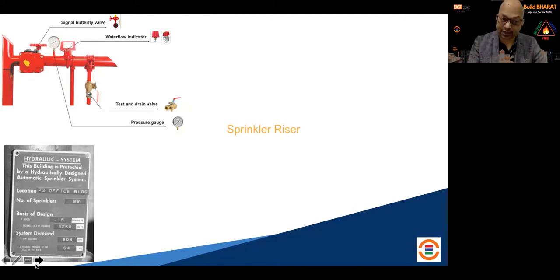So when you do hydraulic calculations, has the design label been followed at site or not? That is again an installation requirement. Not every user actually knows there's a label requirement for every alarm valve and every pump house, where a hydraulically proven system with the right pressure and flow has to be displayed, so that at any point in time your inspection can be carried out.